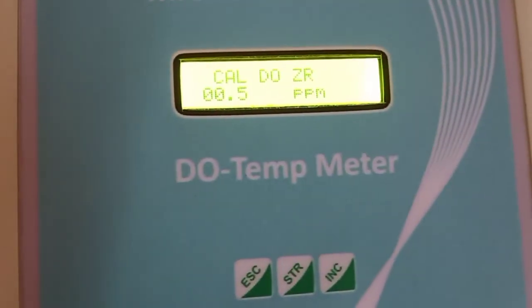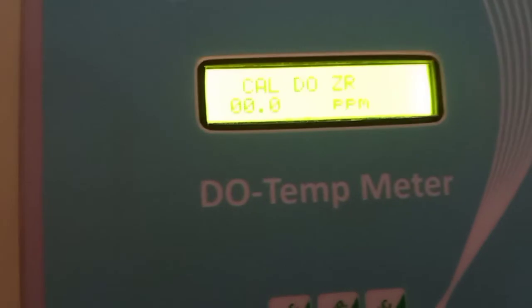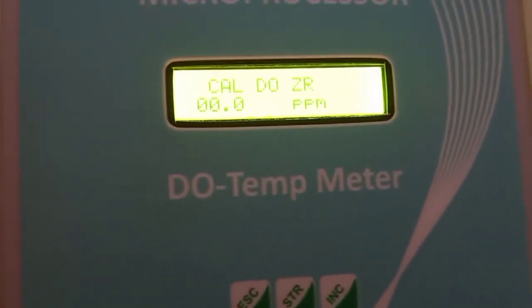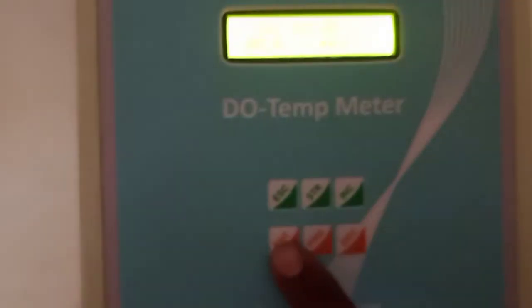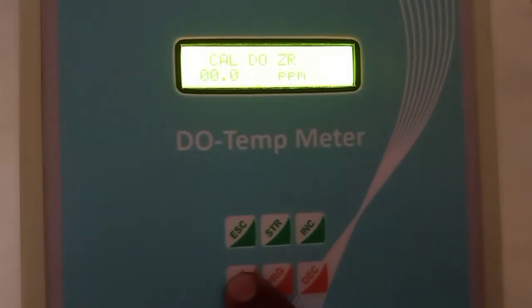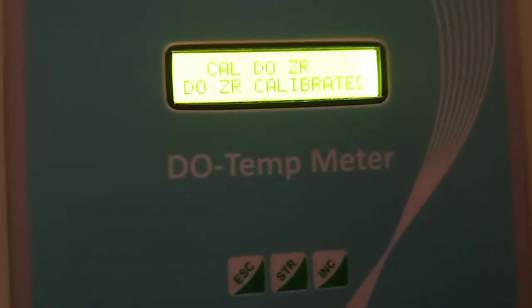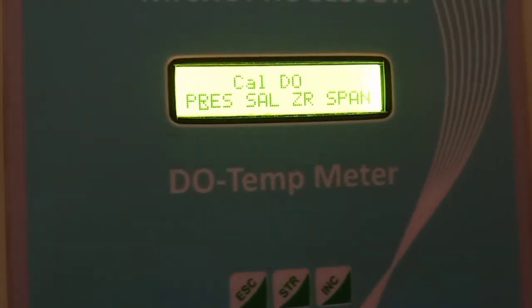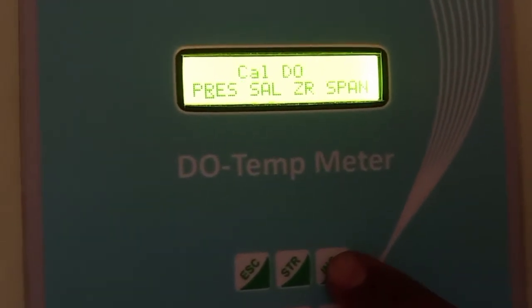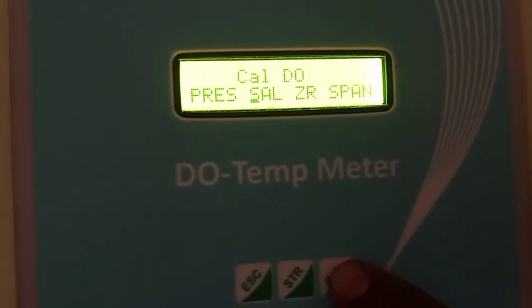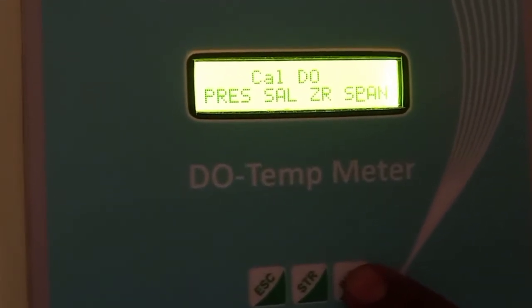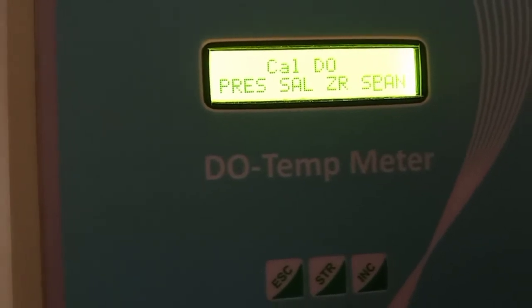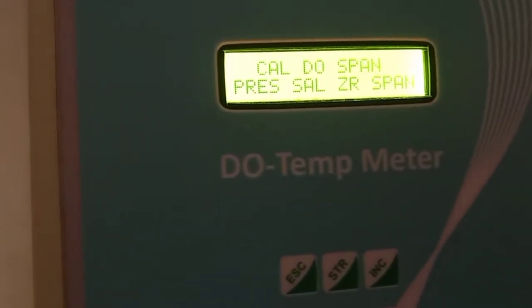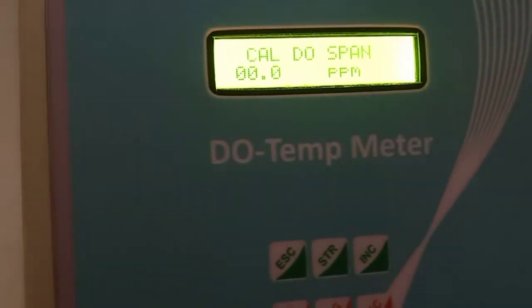Now at that moment, put the electrode into the sodium sulfite solution and wait for the stable reading. Once the readings are stable, press the enter key. Now 0 calibration is over. Now second, we are going to calibrate the standard solution, that is normal water. Move the cursor to span and press enter.